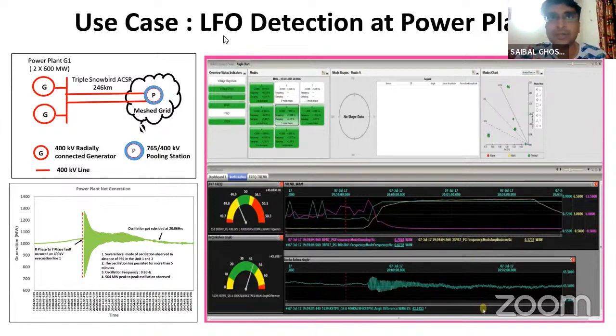Based on the fault level, we know that based on the system strength, the gain parameter needs to be adjusted. So in the STATCOM PODs, this feature is there, they will automatically measure the system strength. How do they measure it? After every day, twice, they will inject some certain amount of MVAR and check what is the change in the voltage. So based on that, they can detect the fault level at that time, and based on the fault level of current time, they change the gain value of their controller.